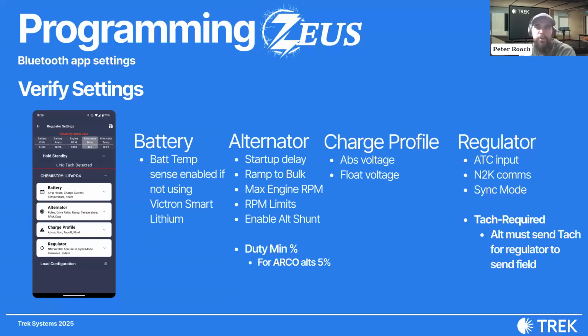One setting here is the duty minimum. For Arco alternators, it's good to set a 5% duty minimum. That plays into the Tach Required setting over on the regulator tab, which makes sure that the alternator must be sending a Tach signal for the regulator to engage. In order for that to work properly, we enable Tach Required, and then we set a duty minimum of 5%, which sends a very small field current to just barely excite the rotor, but not rotate anything, not get it in motion.